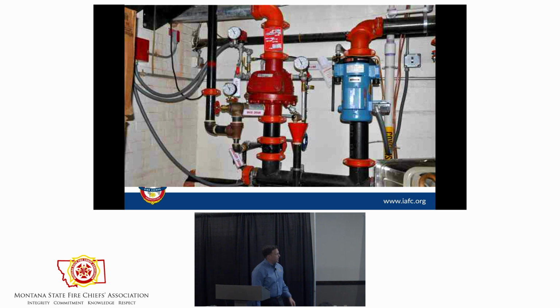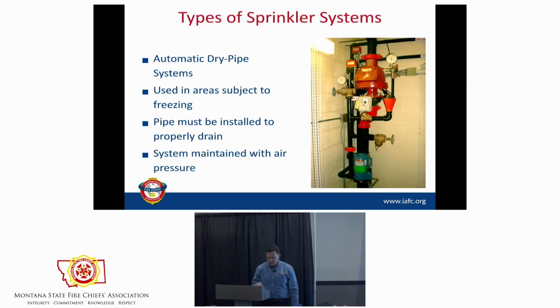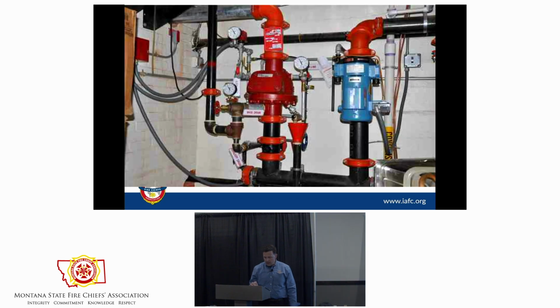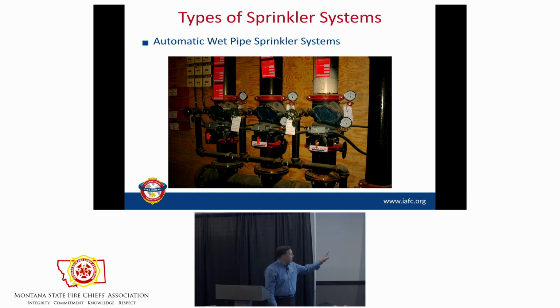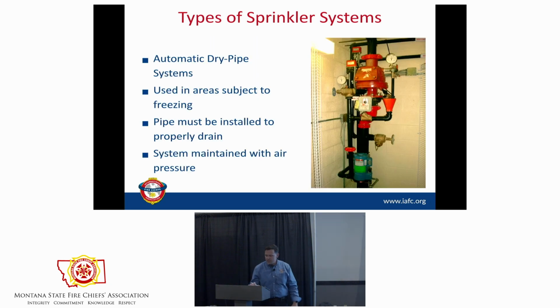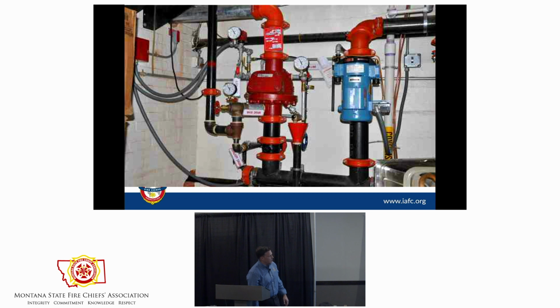First off, you see that thing on the left, wet or dry? Dry. And you're saying dry, why? The bell, okay, so if we look at the bell is a good thing. And then I should have pointed out earlier, but this is another indicator, these double gauges and that flow switch right there. It's a little different than the flow switch on these. Go back. You can't see the flow switches here. These are single check valves. Do you see how it's not really in a bell-bottom shape? That's just a riser check valve, and there's no code requirement for those, but sometimes they decide to put them in. So back to this crazy thing, right?